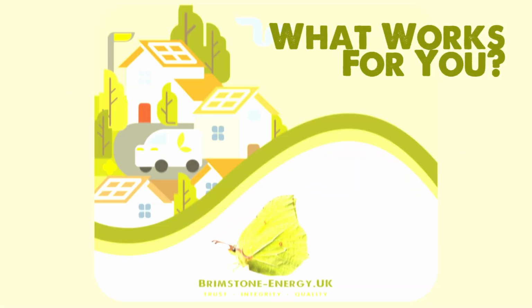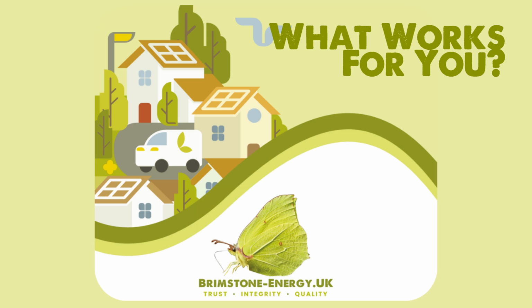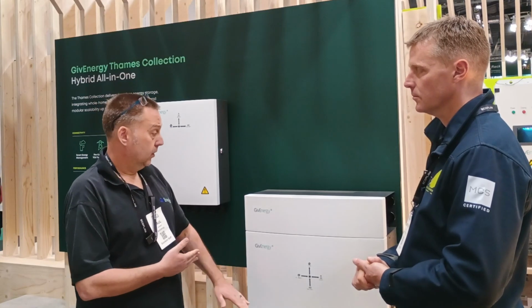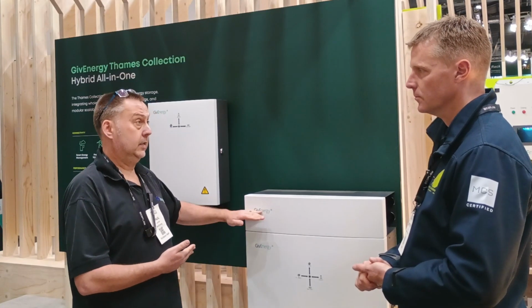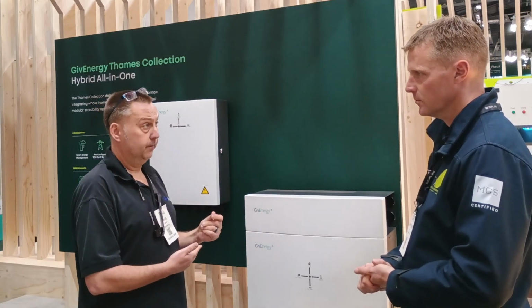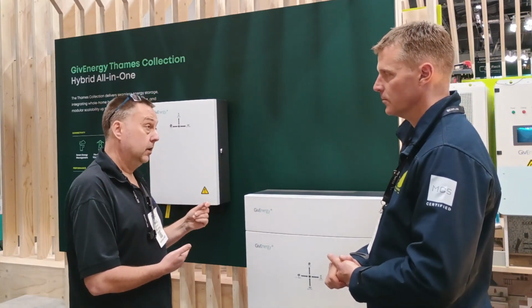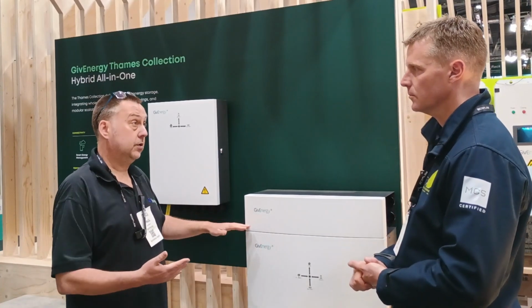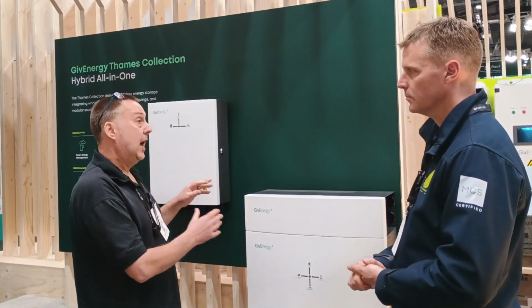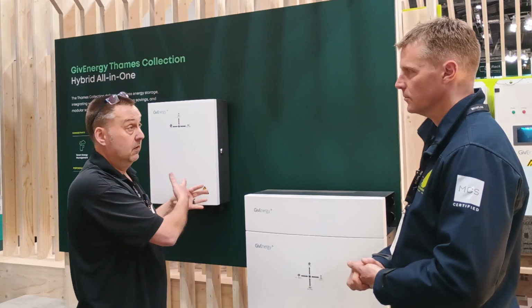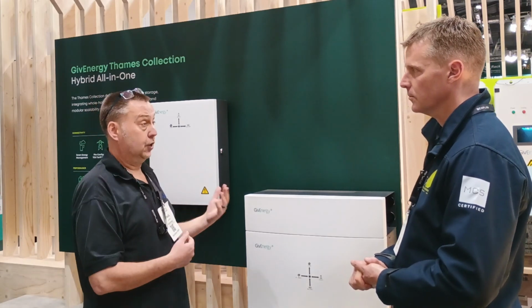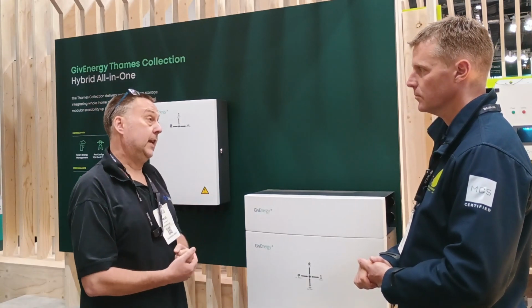So you would program the logic in the gateway at 90%, switch on the smart load. So we charge, we hit 90%, smart load turns on, and the solar is then diverted away from the battery, which sits doing whatever it was doing before, and you then switch on this 3 kilowatt, 5 kilowatt, whatever it may be, extra load to suck up the surplus energy.